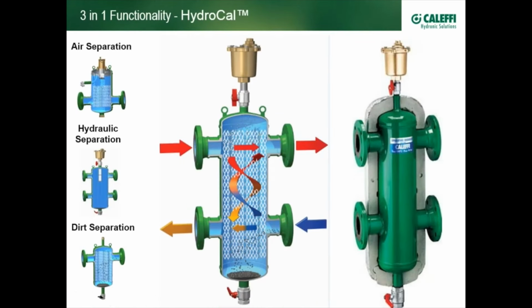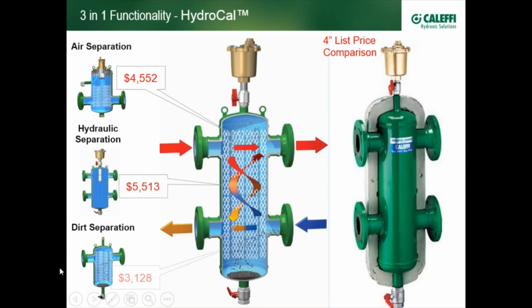Here's an example of why they're so popular. An air separator dedicated here, 4-inch, list price is $4,500 from Caleffi. That function is in the HydroCal. Hydraulic separation, dirt separation, purchased individually, list priced around $13,000 and change. By comparison, the HydroCal, a little over half.